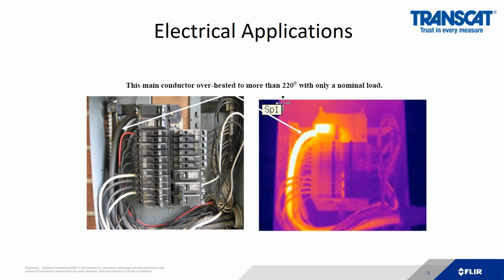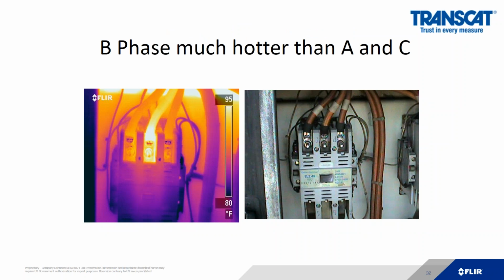And the hotter the target also changes the way you repair things. It's good to know the tensile strength of your metals, so if something got so hot, clean and tighten is not the best response. You might have to disassemble it and put it back together again with new components, because if it got too hot, you might lose the tensile strength of your materials, thereby ensuring once you fixed it, you'd have to go back and fix it again after it loosened up.